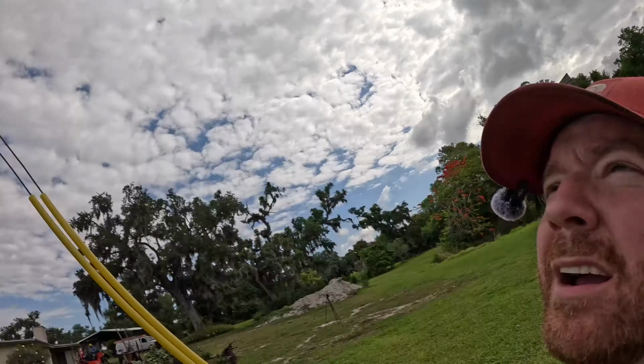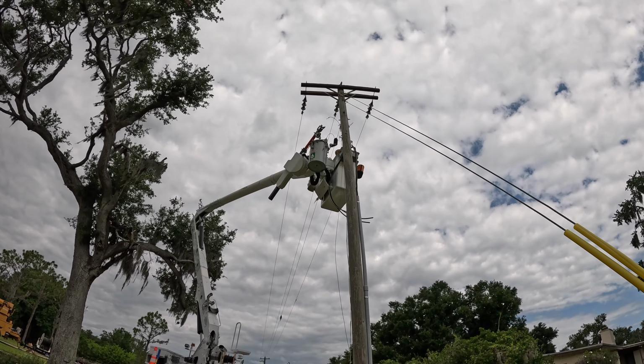If you wanted an open point for like a clearance or something, they would have to go all the way back three-quarters of a mile up the line and open up the cutout on the B phase at the pole at the road over there. But they'll install a cutout switch on this one if they ever need to come out and pull it with a hot stick to do work.